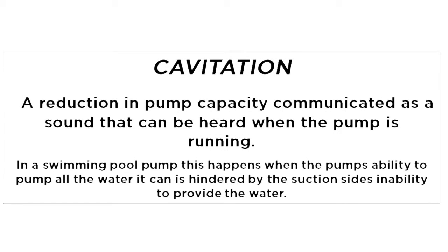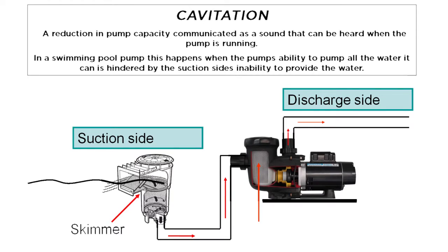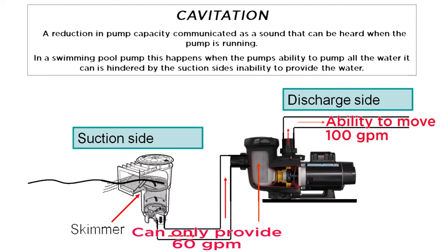Cavitation: in a swimming pool pump, this happens when the pump's ability to pump all the water it can is hindered by the suction side's inability to provide the water. If a pump on the discharge has the ability to move 100 GPM but the suction side can only provide 60 GPM, you have a pump that cavitates. The pump trying to get 100 GPM from the suction side will pull air out of the water, causing bubbles in the pump basket and a noisy pump. This can cause damage to the pump if not corrected.